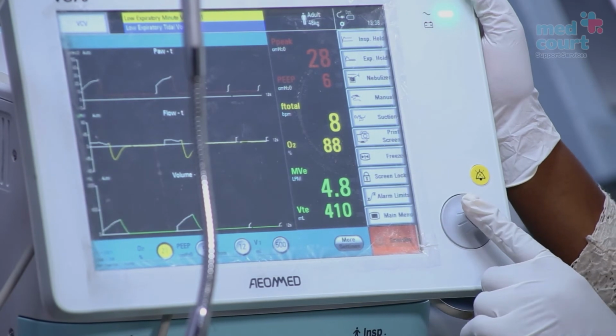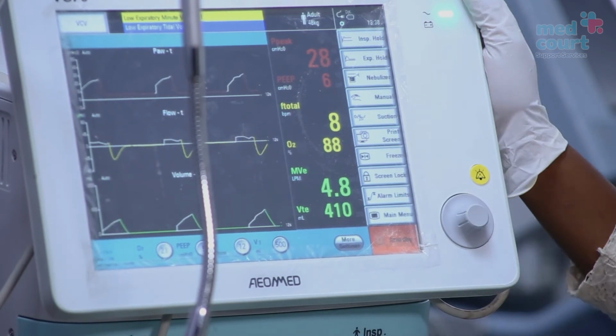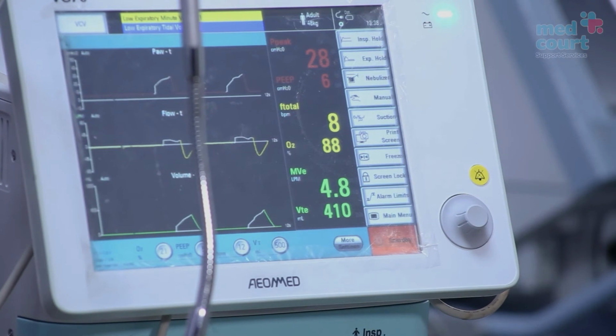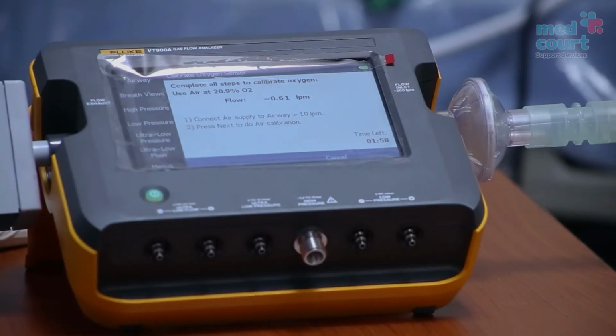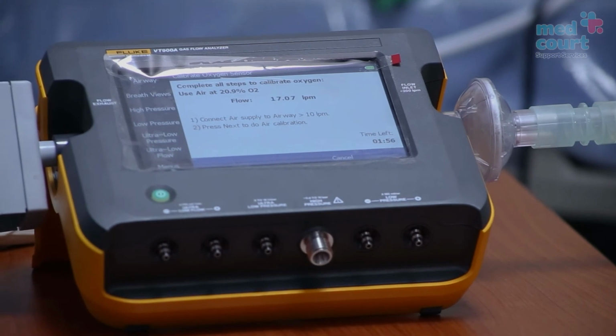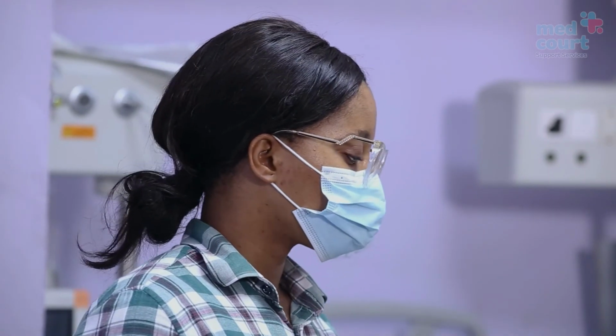And then we enter. Click Next on the VT900A. Calibration takes 2 minutes. Once calibration at 20.9% oxygen has been completed, set the oxygen concentration to 100% oxygen.